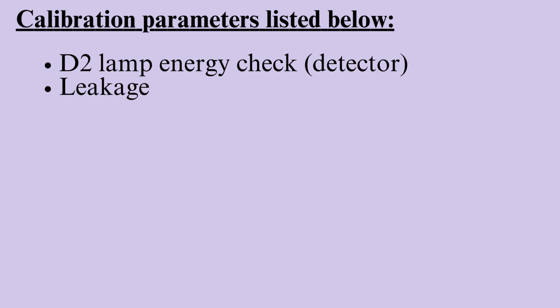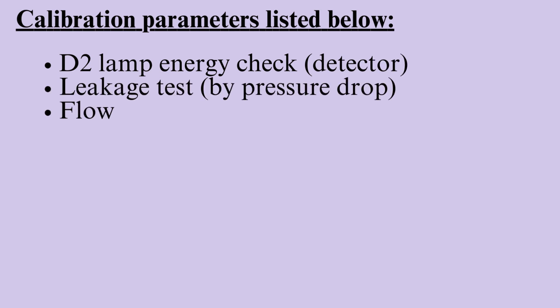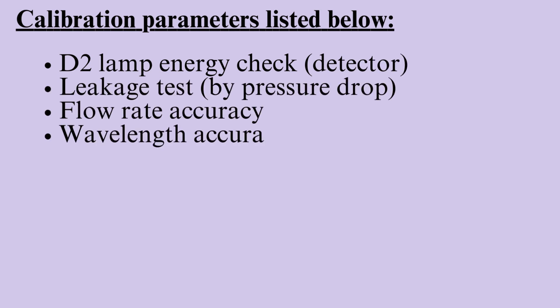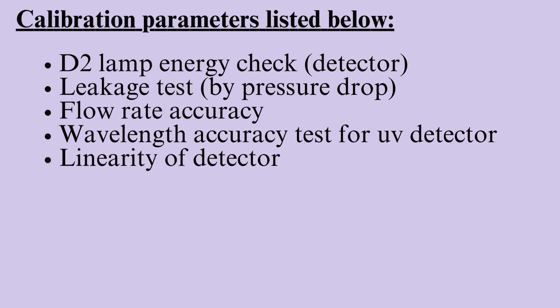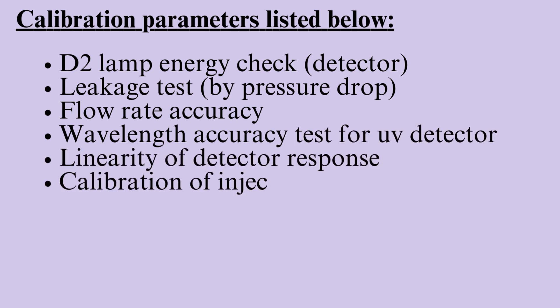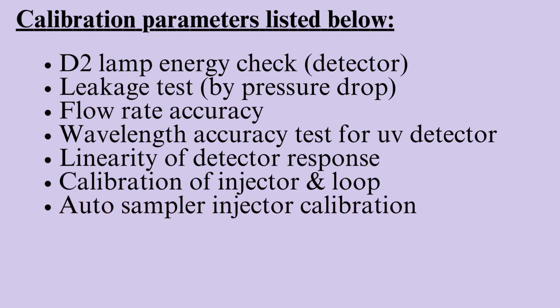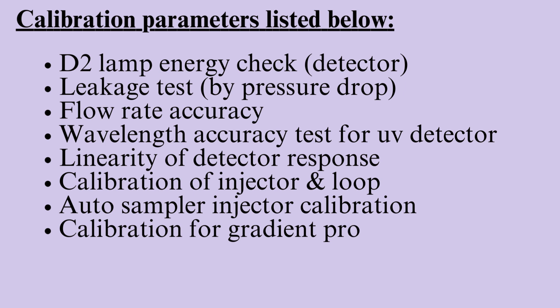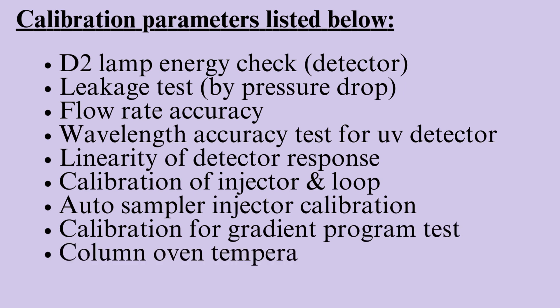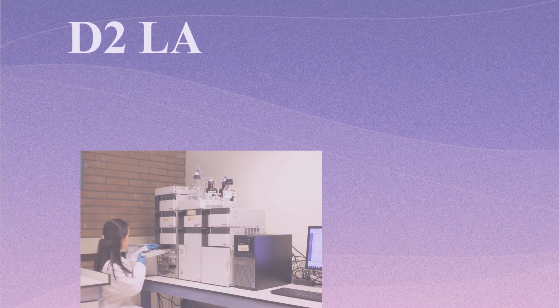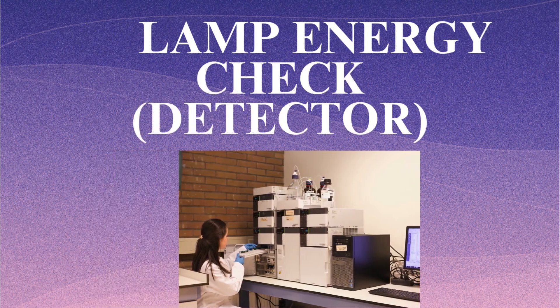Calibration parameters listed below: D2 lamp energy check, detector leakage test by pressure drop, flow rate accuracy, wavelength accuracy test for UV detector, linearity of detector response, calibration of injector loop, auto sampler injector calibration, calibration for gradient program test, column oven temperature, carryover test, and D2 lamp energy check detector.